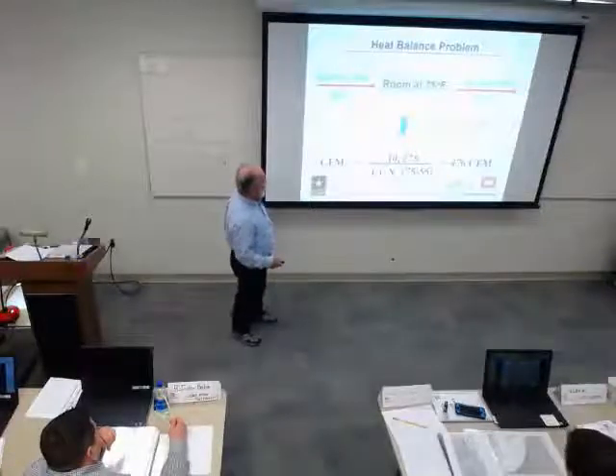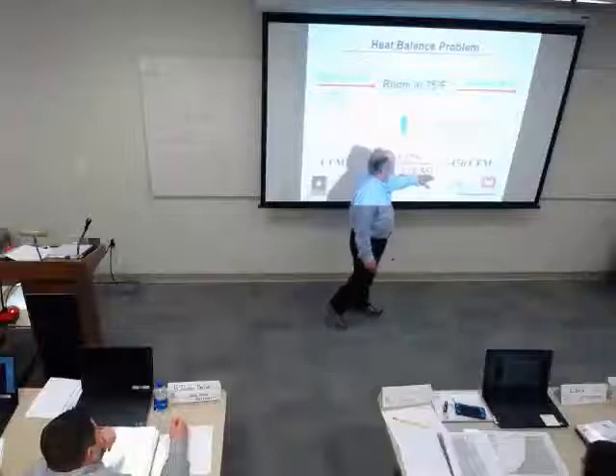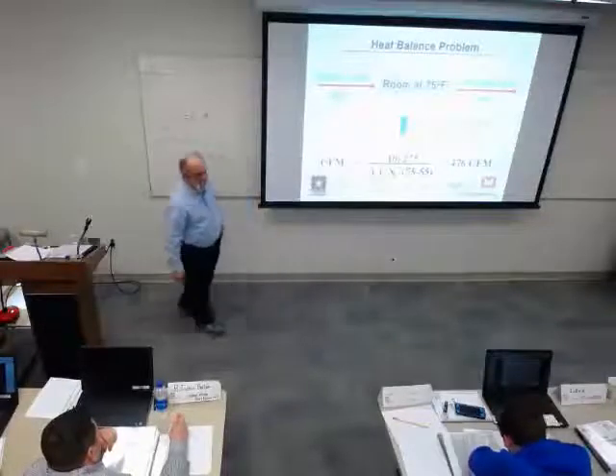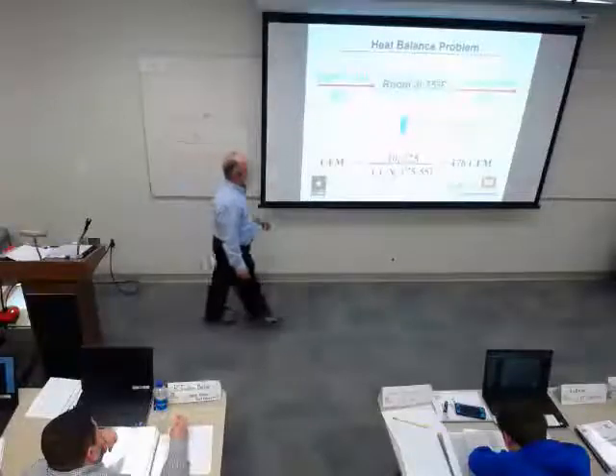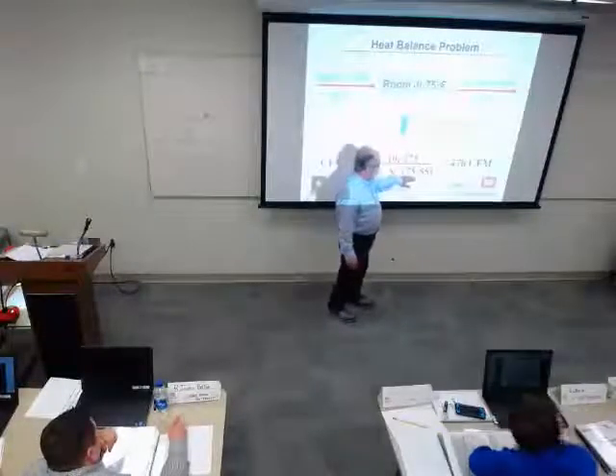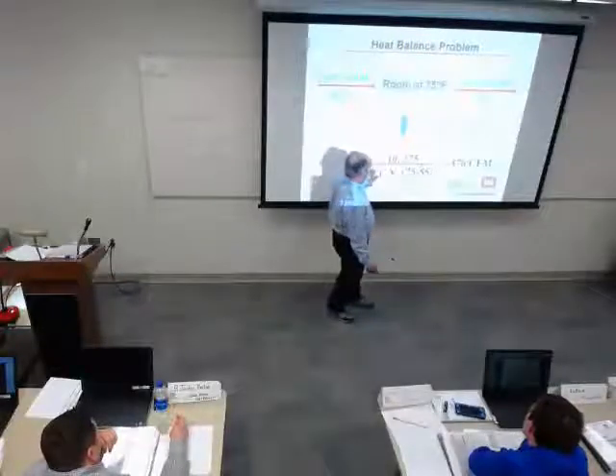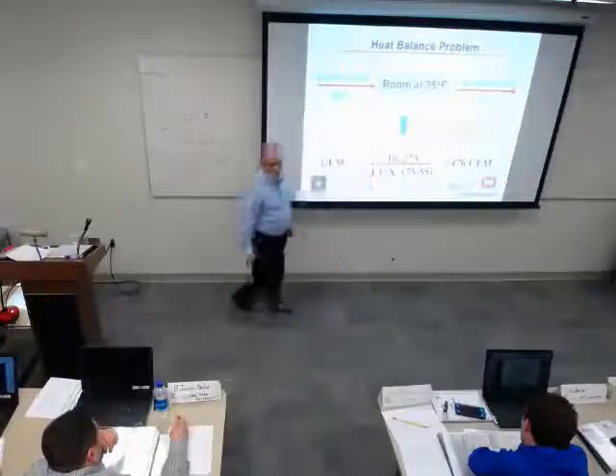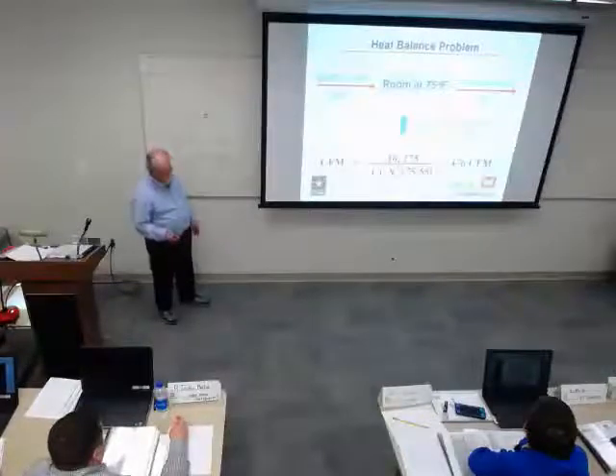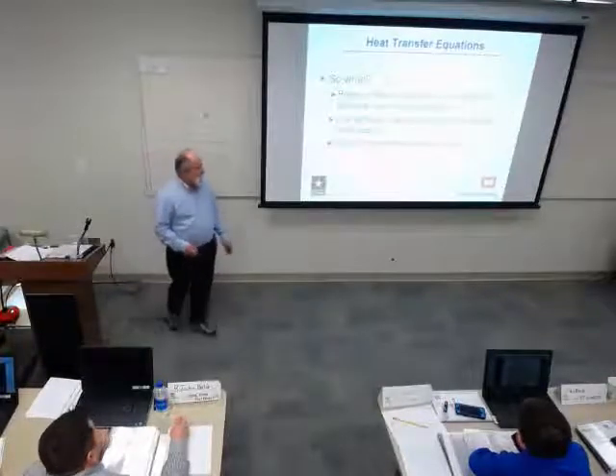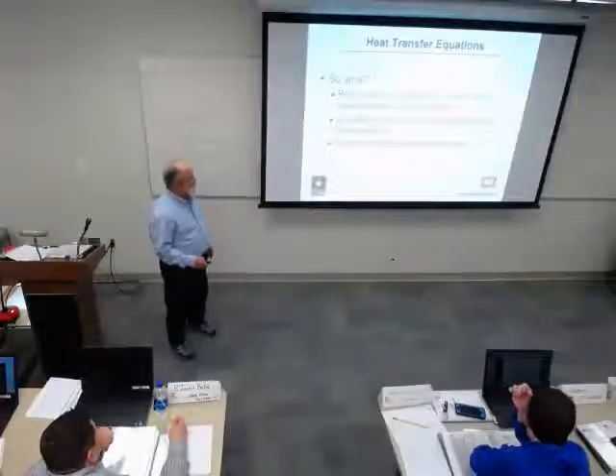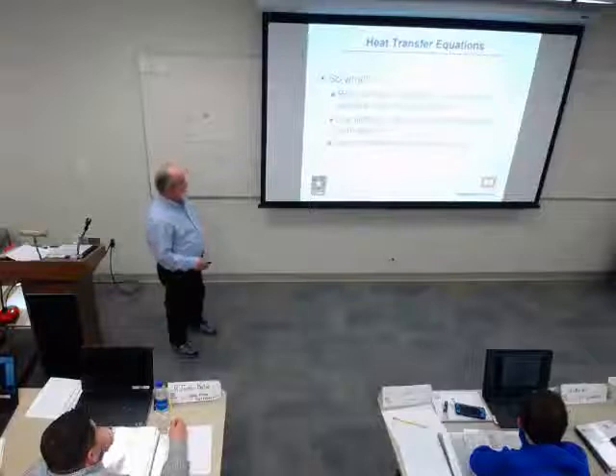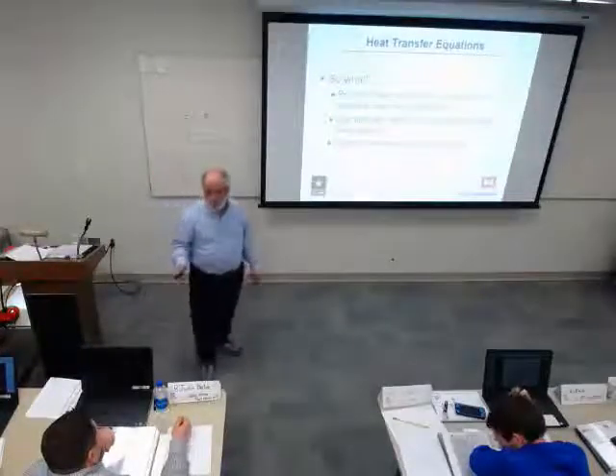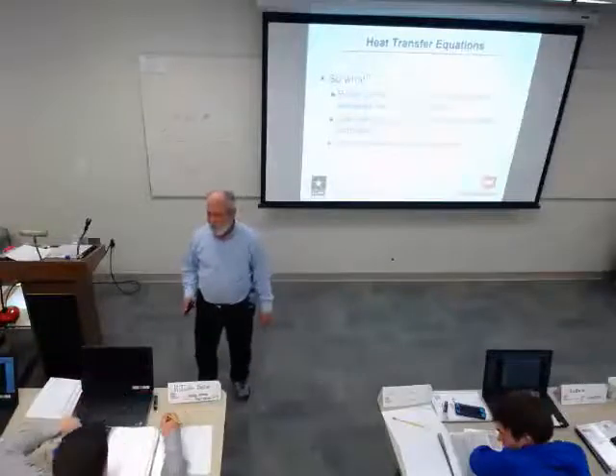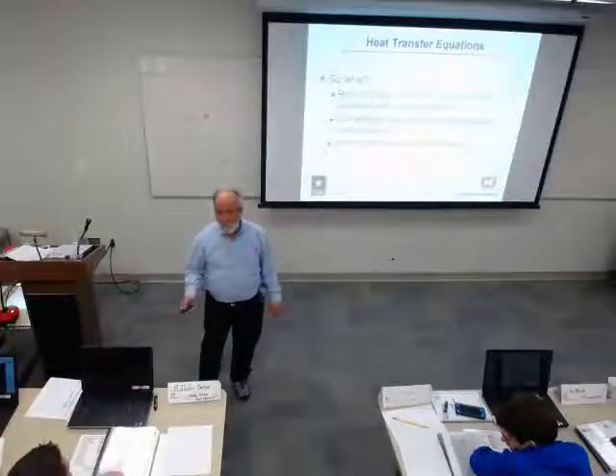And we end up with, we've got to have that condition in the room, we have to have 476 CFM. Now, as you can see right here, if we left at 80 instead of 75, that would make this number down here bigger, which would mean that this number over here would be smaller, because if we divide this by a bigger number, that gets smaller. Okay, so what we just saw there was that the room airflow is related to the amount of sensible heat that's removed or added.